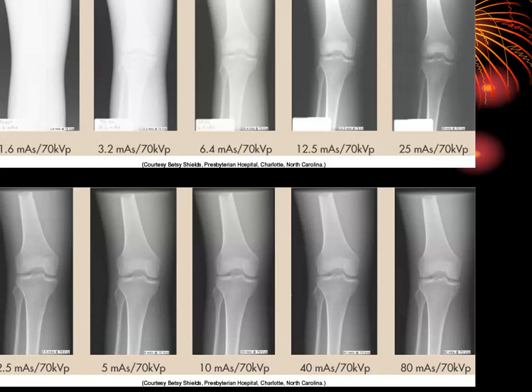Looking at a comparison image: the top row uses film screen at 70 kVp, ranging from 1.6 to 25 mAs — showing progression from high contrast/white to a slightly overexposed darker image, with about 12 mAs appearing optimal. The bottom row shows a DR system from 2.5 to 80 mAs with no significant change in density or contrast — the images all look good. Shooting at 40 mAs is totally irresponsible; please don't do that.